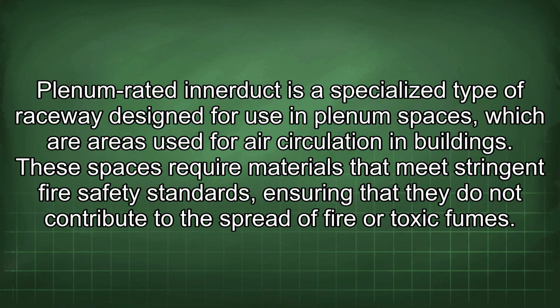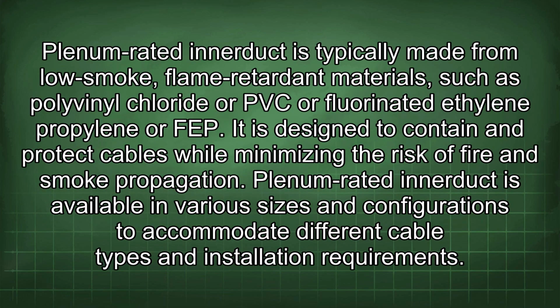Plenum-rated innerduct is a specialized type of raceway designed for use in plenum spaces, which are areas used for air circulation in buildings. These spaces require materials that meet stringent fire safety standards, ensuring that they do not contribute to the spread of fire or toxic fumes. Plenum-rated innerduct is typically made from low-smoke, flame-retardant materials such as polyvinyl chloride or PVC or fluorinated ethylene propylene or FEP.